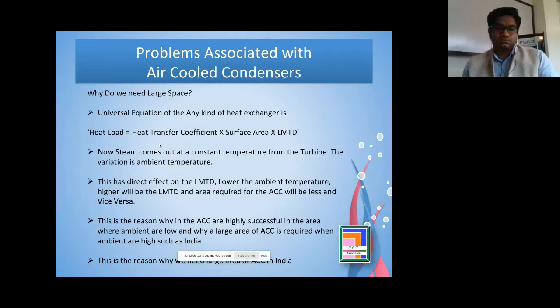So what happens in the case of high ambient? Why do heat exchangers or air-cooled condensers have a limitation at higher temperature? See, there is a universal equation. Heat load is equal to the heat transfer coefficient into the surface area into LMTD. And we are all engineers. We know all these equations.